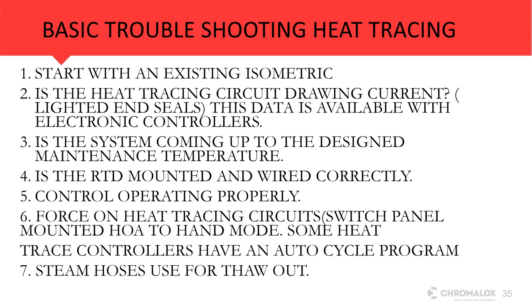Is the system coming up to the design maintenance temperature? Look at that and see, is the RTD mounted and wired correctly? I've been to many projects where someone's gone back and done some work and the RTD's out there hanging in open air. So it's sensing ambient temperature instead of line temperature, and the system's not operating properly. Are my controls set up properly? Did someone go in and change the set points from what we had in the original design?